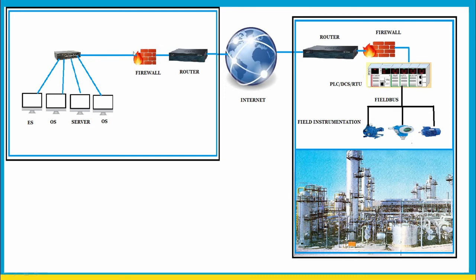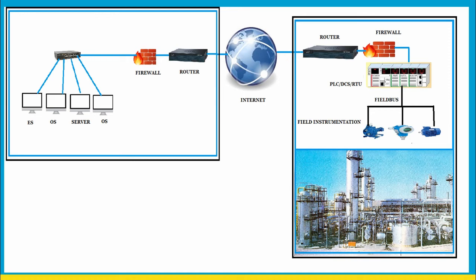Then there comes the firewall. Firewall is just like a security guard. It's at the door of your house and it's protecting you, like security guards at your door of your organization or door of your house to protect your organization or house. Same is the case when we talk about industrial control system. If we put in a firewall, so that firewall is like a security guard protecting your control system from unauthorized access. Only specified ports, only specified source and destination IP addresses and host names should be allowed in firewalls. And firewalls should be configured properly. Only specified ports that are required for the communication should be opened. Rest of the things should be kept blocked.